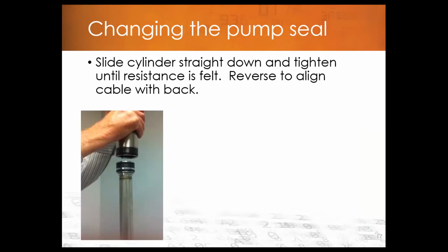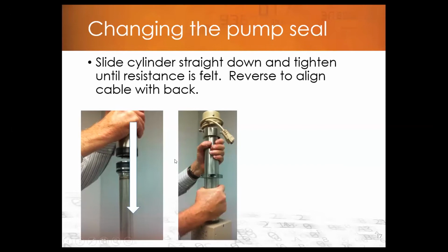And once you've got your piston seal replaced and the retainer back on and tightened, you'll want to slide your cylinder back down over the piston. And it's just basically you guide it onto the piston, make sure that you're fairly well centered when you put it over the seal, and then basically just start pushing the cylinder down until you've got it all the way down into the mount, and you start tightening it into the cylinder mounting block.